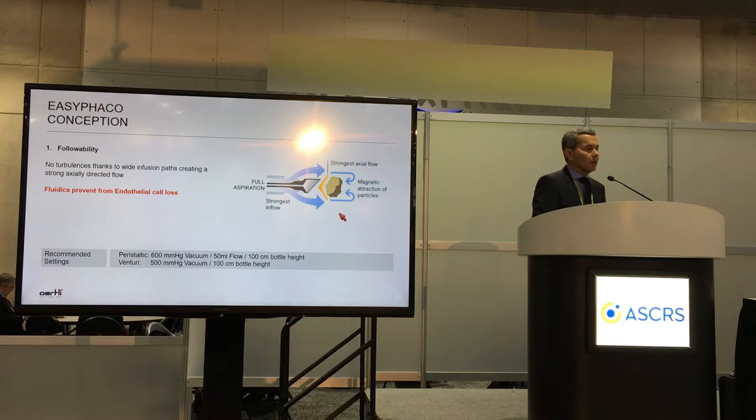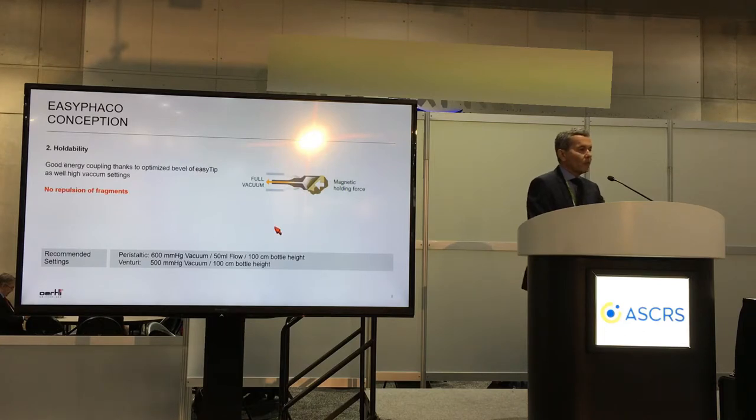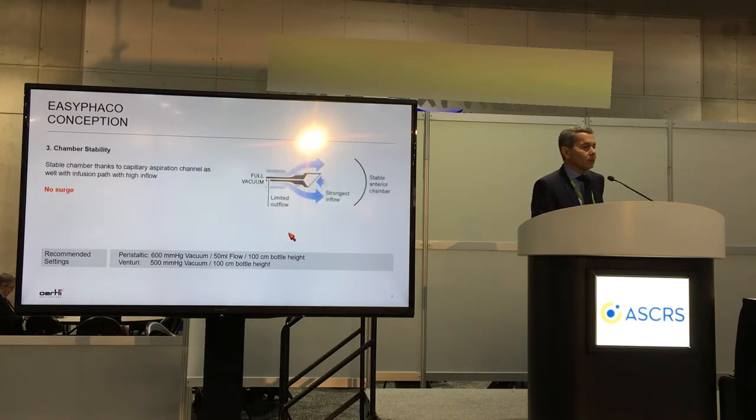We also have a widening infusion line that allows much more fluid capacity on the infusion compared to standard EasyPhaco. For followability, there's no turbulence thanks to the wide infusion paths creating a strong axial directive flow with a magnetic attraction of particles. There's virtually no repulsion of fragments because the large amounts of tissue can be held in full vacuum, and there's virtually no surge, limited by the very narrow 450 micron aspiration path.